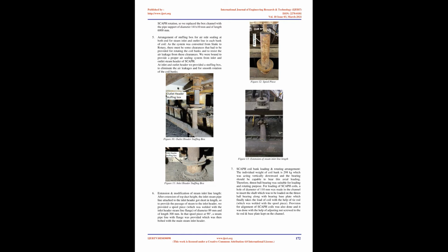There were many ideas which were pondered over to reduce auxiliary power consumption associated with the SCAPH system. Firstly, we thought of eliminating the SCAPH permanently from the system, but it would have left no option to help during times of cold and corrosion prevention. The second idea was to make an investment on erecting a bypass duct with an additional path for air to the SCAPH system and to erect additional dampers for isolation during non-usage period. But it would be bulky and would require space.